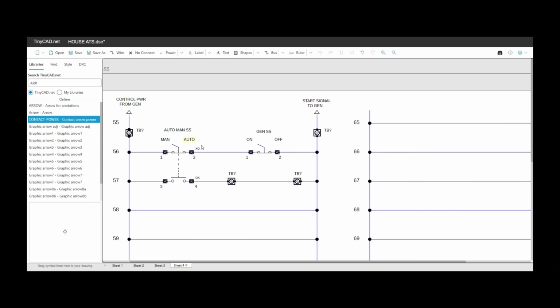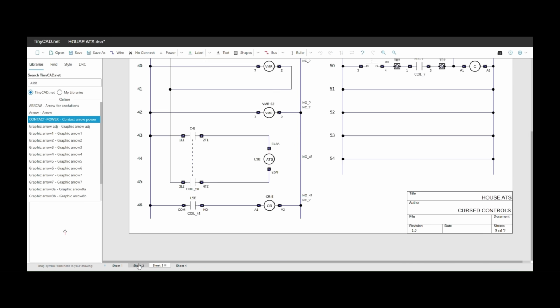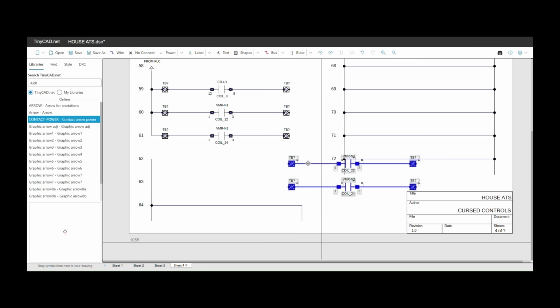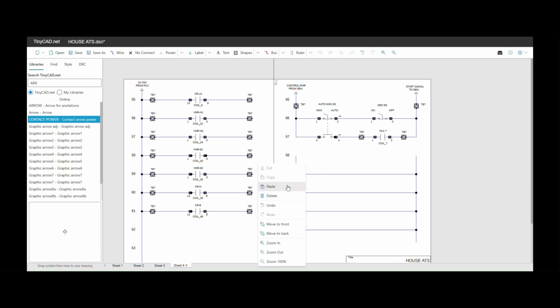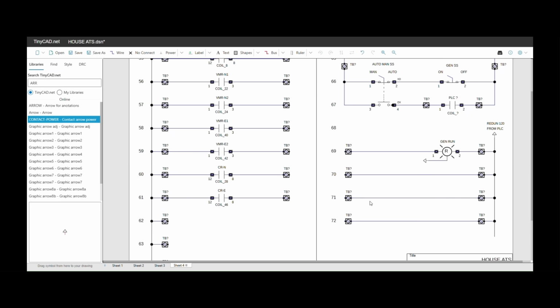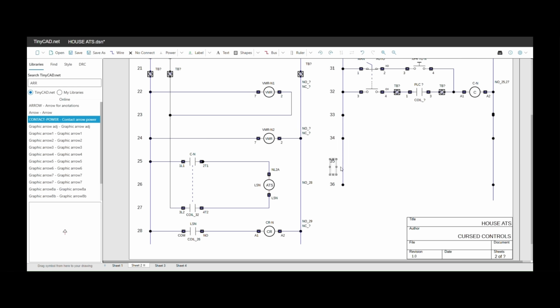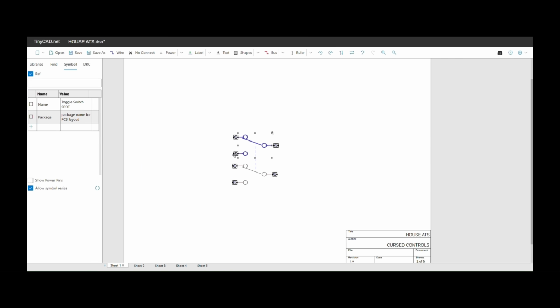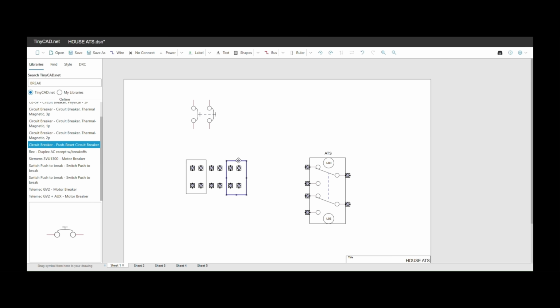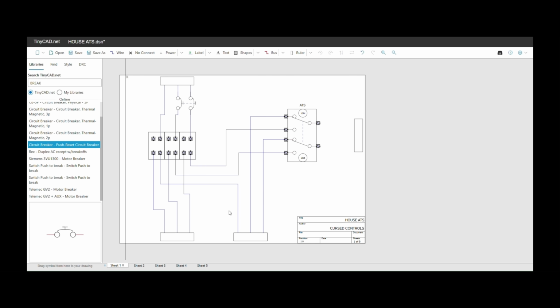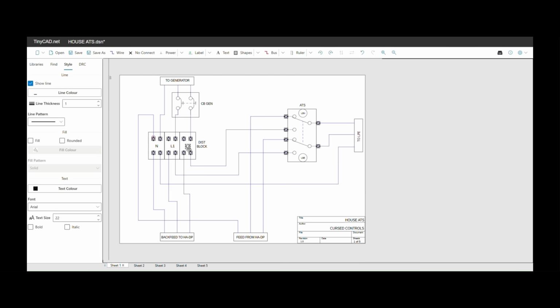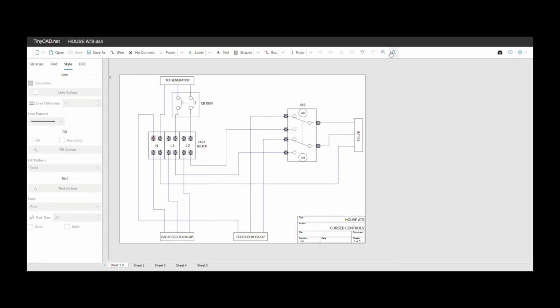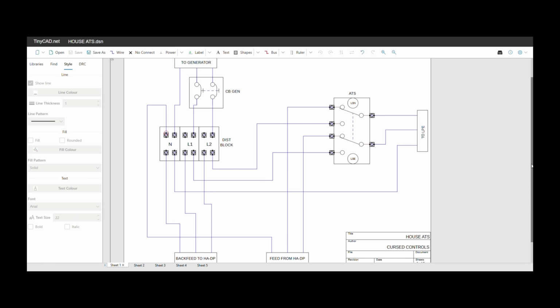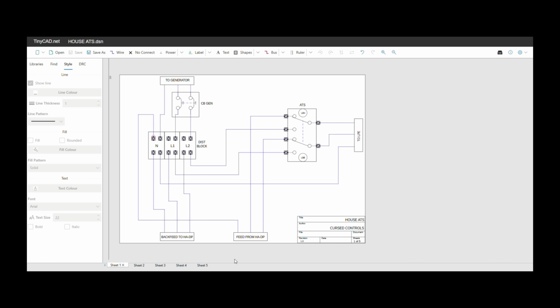Basically I'm just creating a caveman version of a transfer switch. I'm taking a perfectly good ATS and making it much more complicated. I'm going to use actual voltage monitor relays that can be easily replaced, and all of that's going to go back to my PLC panel. The PLC is going to be the brain of this operation, controlling all the timers, the transfer, the auto exercise, all that good stuff - that's already in that circuit board. I'm going to make it all go through the PLC.